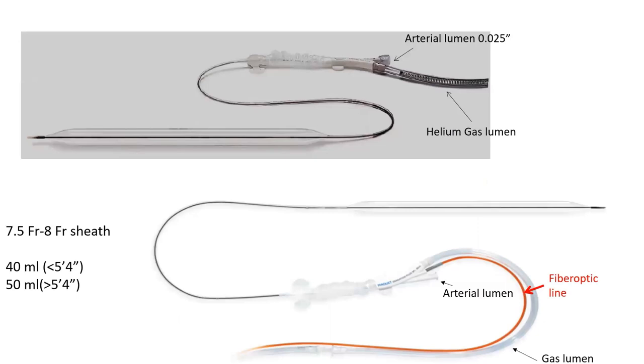I will move on to describe the balloon pump catheter. So this is the balloon pump catheter. This is the traditional one. And you have two lumens. It's very simple, two lumens. One lumen is the helium gas lumen, which is connected to the balloon and allows balloon inflation. And the second lumen is the central arterial lumen, which connects to the tip and allows monitoring of the aortic waveform and of the proper augmentation of the arterial pressure.